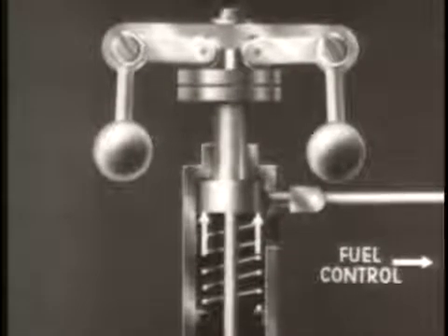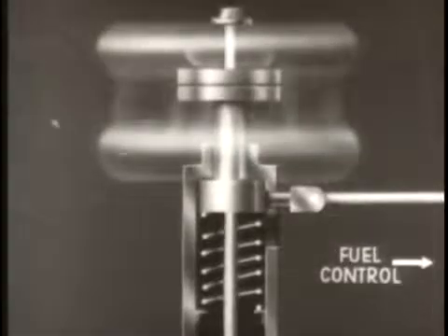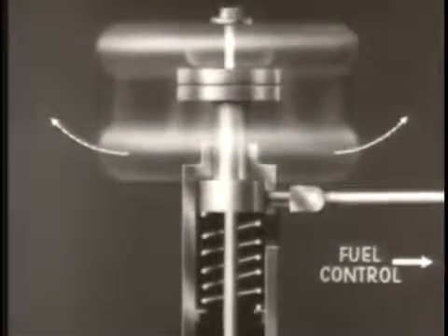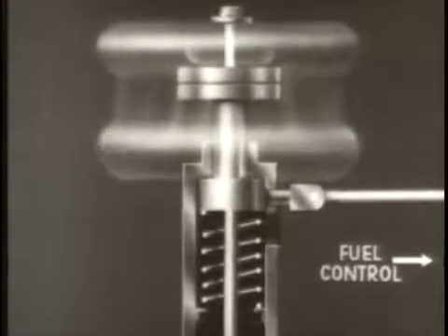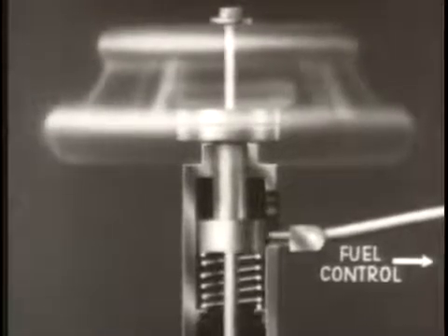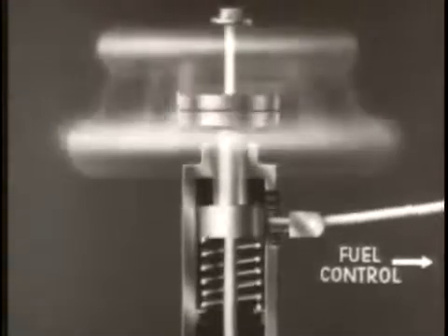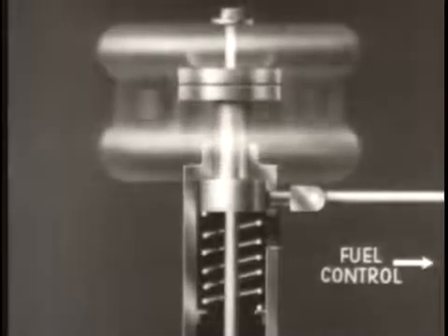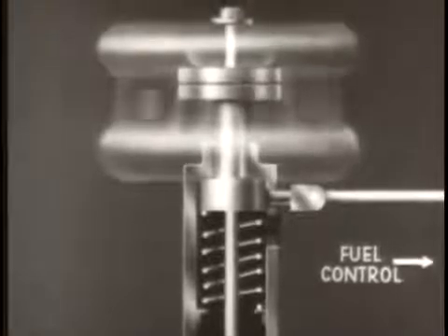A spring presses upward against the collar. As the engine operates at normal speed, the flyweights tend to move outward. This movement, however, is retarded by the spring. But should the engine speed increase to a point where the safe speed limit is exceeded, the centrifugal force of the flyweights becomes great enough to depress the spring. This actuates the linkage to the fuel pump control, reducing the amount of fuel injected, and a decrease in engine speed results. Thus, the overspeed governor serves as a safety device in preventing the diesel engine from overspeeding.